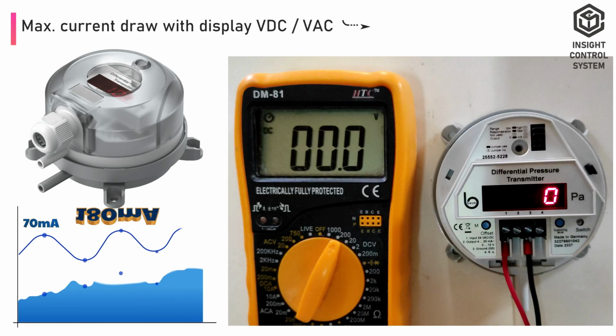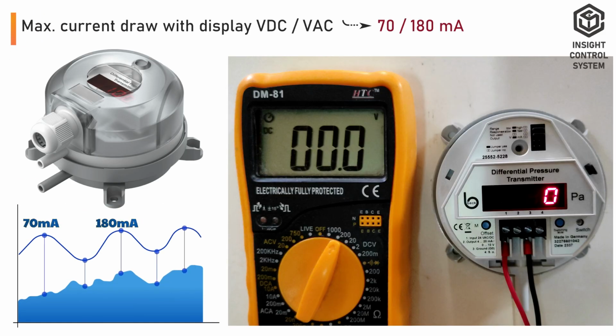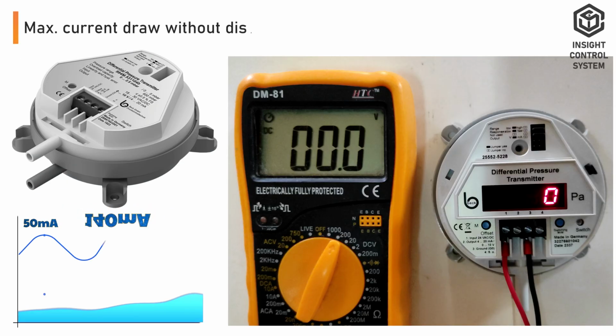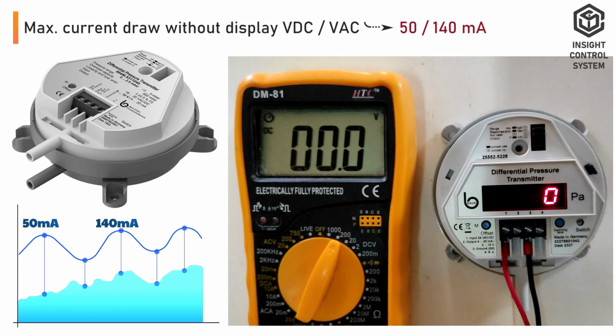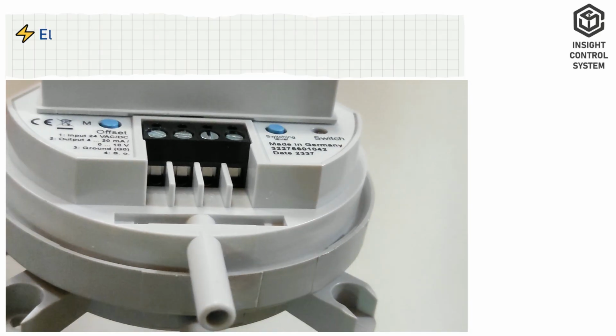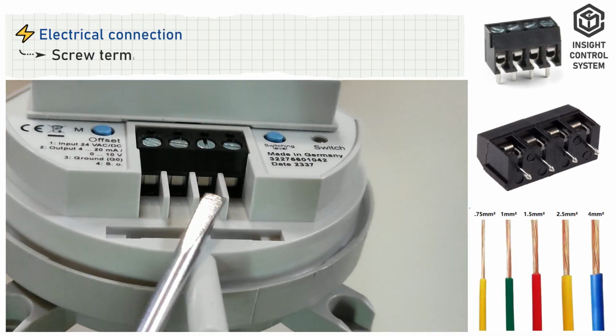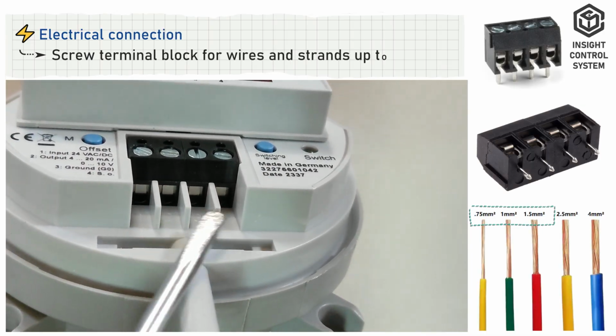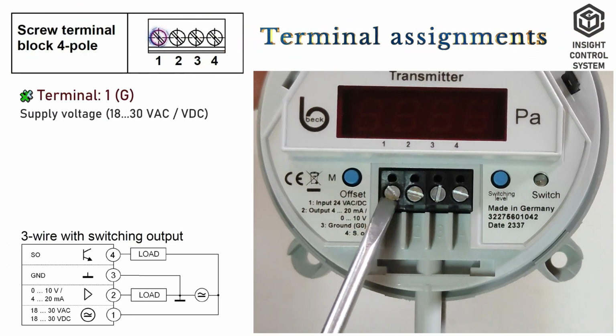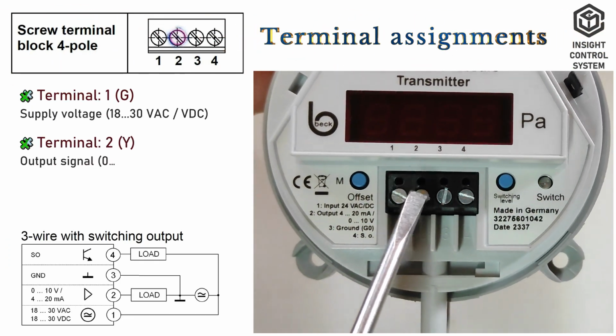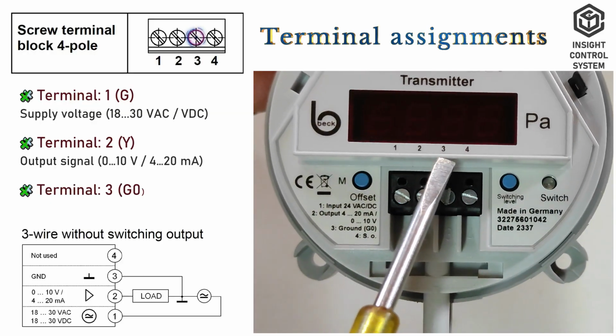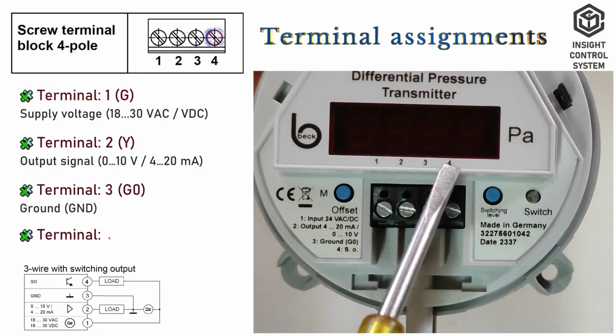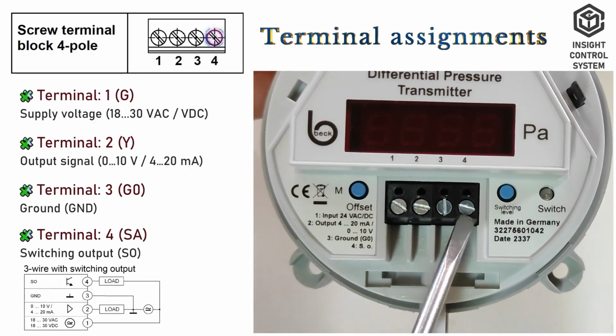Maximum current draw with display for DC is 70 mA and AC is 180 mA. Without display for DC is 50 mA and AC is 140 mA. Terminal connection. Electrical connection is screwed terminal block for the wires and strands up to 1.5 mm². Terminal 1 or G is supply voltage. Terminal 2 or Y is output signal. Terminal 3 or G0 is ground. Terminal 4 or S is switching output.